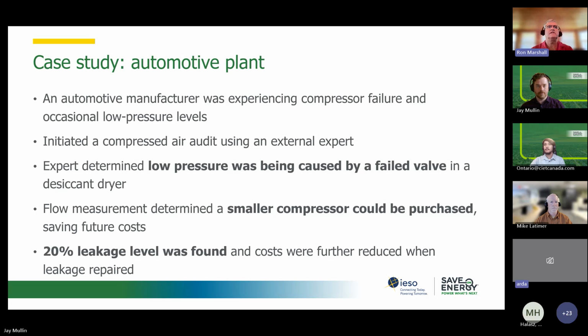And in the meantime, we could see the flow measurements. If they fix that failed dryer, they could replace this failing compressor with a smaller compressor, saving future costs, right? And we also found a 20% leakage level. We could tell that from the flow meters. And if they fix this, they could have further reduction in cost. And if they did their compressor control well, they could gain a lot of savings from their efforts. If the compressors were controlled poorly, then the savings are not as much.